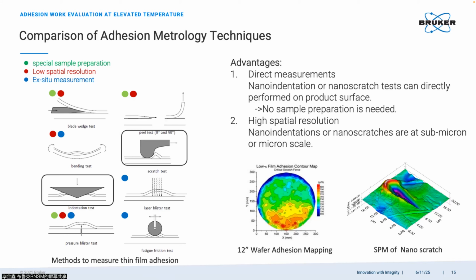And not to mention this one, which I would say is the most challenging one. We call it the back hole method. You need to drill a hole from the backside of the substrate, and you need to be very careful not to damage the interface. Then you insert a certain pressure to delaminate the interface. It is a very difficult thing to do. So for the indentation method and scratch method, you don't need to prepare your sample. For a typical wafer form, you can put your wafer in and we apply our probe directly onto your top layer to induce the interfacial debonding. That is the first advantage, direct measurement.